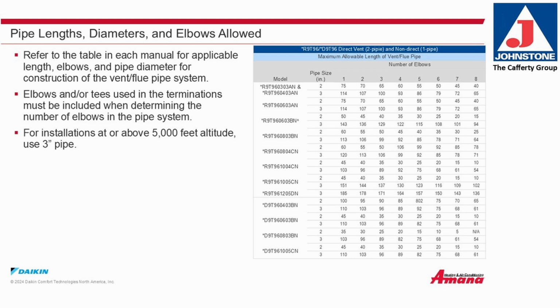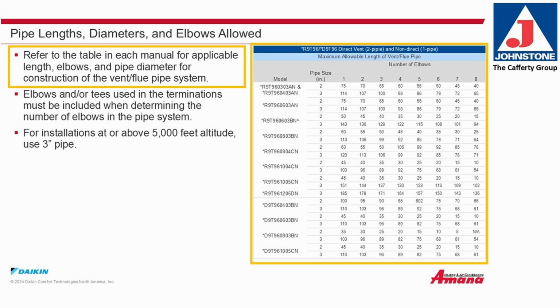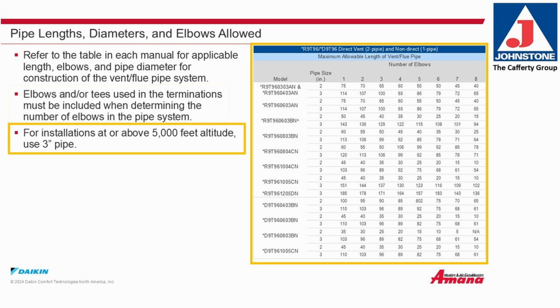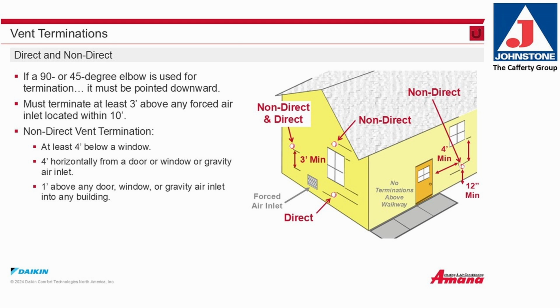Pipe lengths, diameters, and elbows allowed. Refer to the table in each manual for applicable lengths, elbows, and pipe diameter for construction of a vent flue pipe system. Elbows and/or T's used in the terminations must be included when determining the number of elbows in the pipe system. For installations at or above 5,000 feet altitude, use 3-inch pipe. Vent terminations, direct and non-direct. If a 90 or a 45-degree elbow is used for termination, it must be pointed downward. Must terminate at least 3 feet above any forced air inlet located within 10 feet.